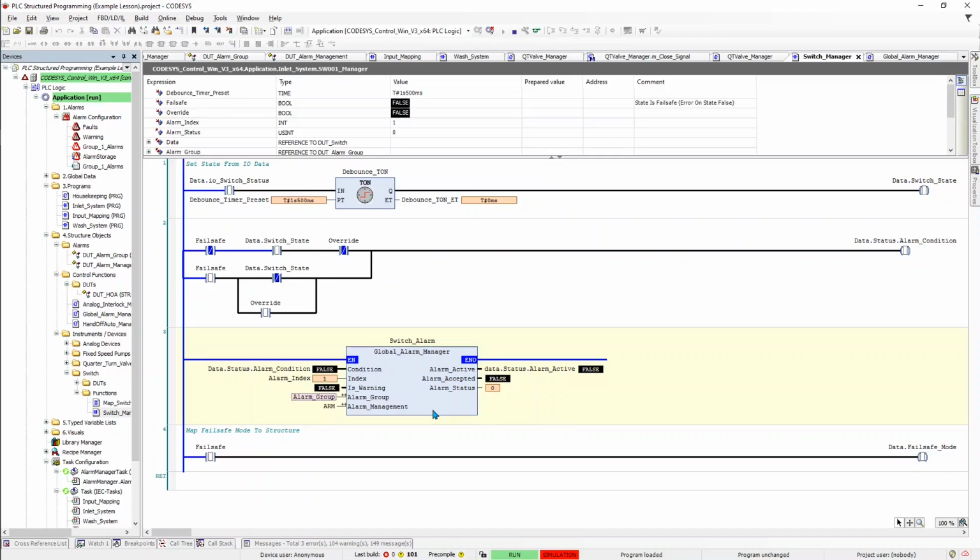In fact, in other projects, in one that I have the system set up in Siemens TIA Portal as well, I have 15 groups in a particular project, and I'd say around half of the alarms out of all of those groups are populated. So there's a considerable amount of information there, and I don't have any problems with scan time doing it this way. So it's a really good way of passing alarm information around your project, and when you're ready to add a new alarm to the system, your structure's already there. You simply assign the number and off you go.